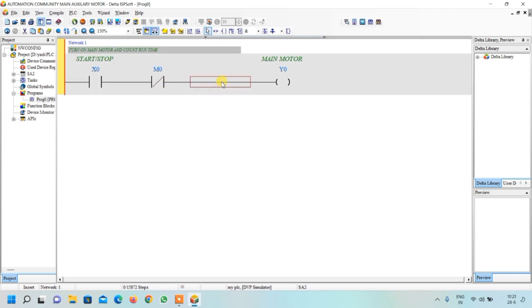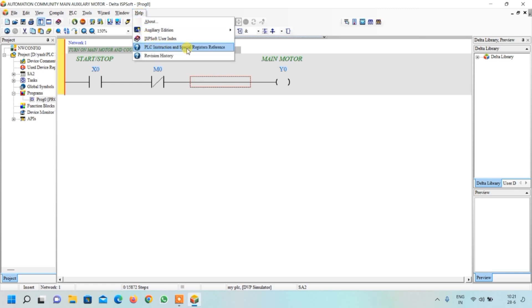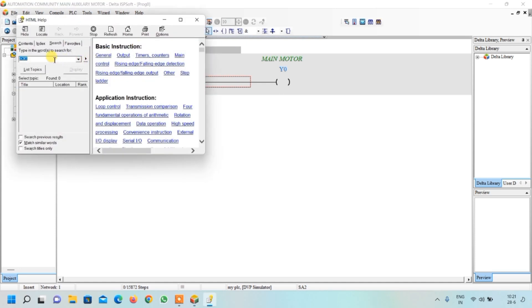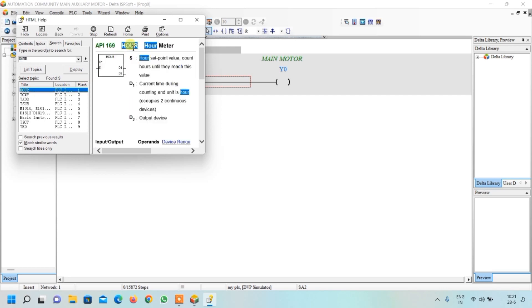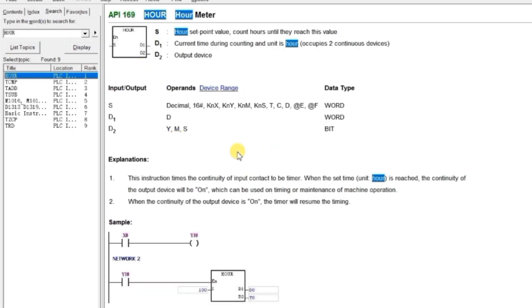Now we want to count the running time of this motor — how many hours it has run. For that, we will look at the HOUR instruction. Click on the Help menu and select PLC Instruction and Special Register Reference. Type HOUR and press Enter, then double-click on the first result. This is the new instruction we are going to use today — its name is HOUR and its mnemonic is also HOUR.